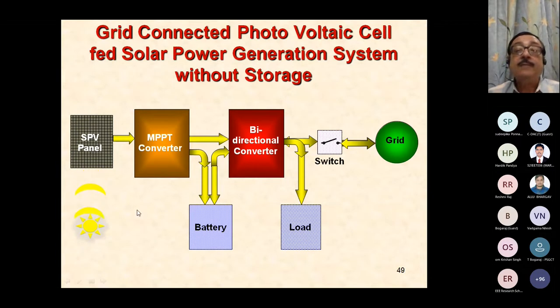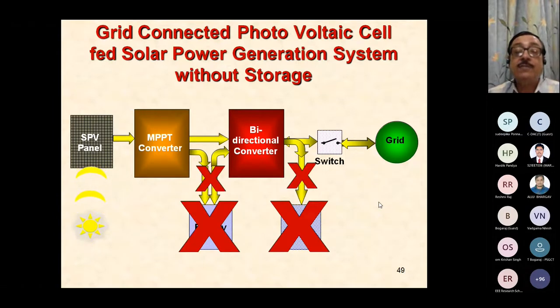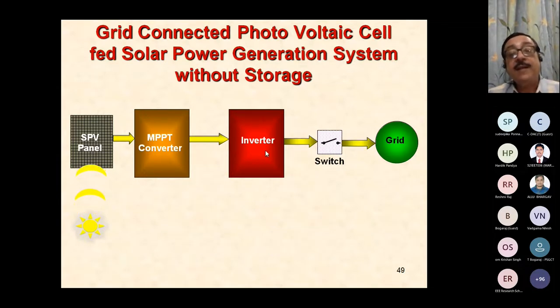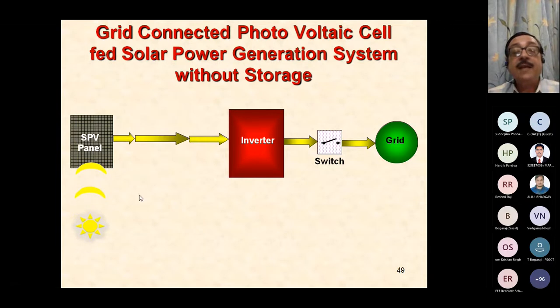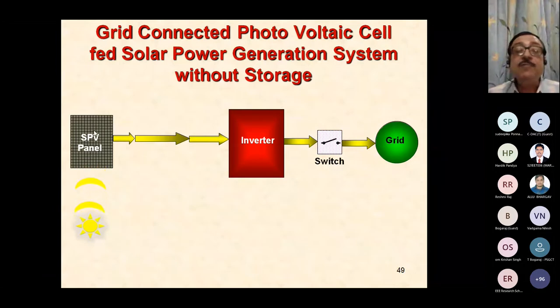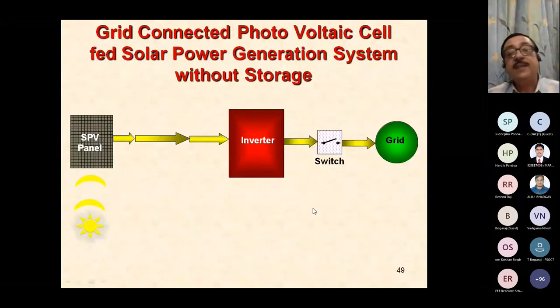Okay. Now, you can go in for a system, like I mentioned, without storage. So you don't have a local load, which means you don't need the battery. So all these are cut out. You don't need them. So in this case, you can get rid of the word bidirectional converter and say inverter, and you can further get rid of the MPPT converter and connect it directly, because the function of the maximum power point tracking can be done by the inverter itself. There is nowhere else that the power is flowing. The power is flowing through the inverter, so the inverter can control the amount of power that's flowing out. So that means you are having indirect MPPT operation, because MPPT is maximum power point tracking. So the inverter does everything there.